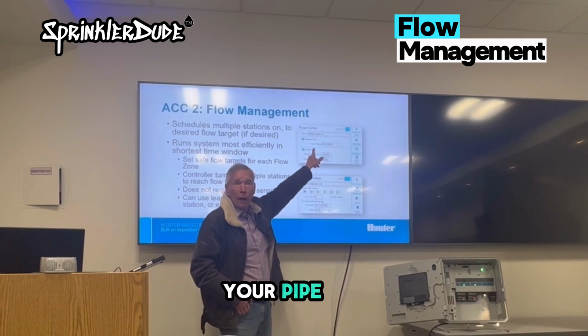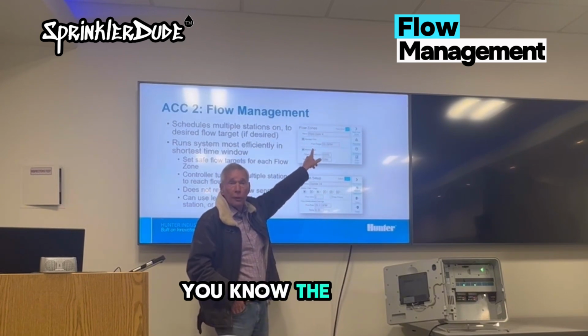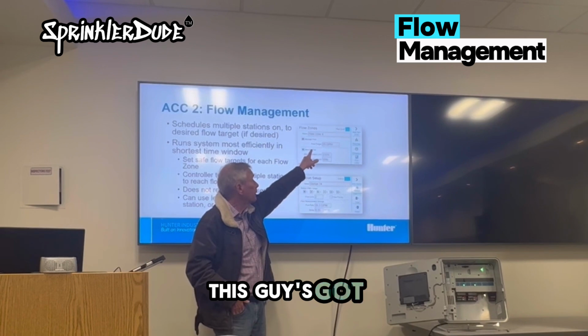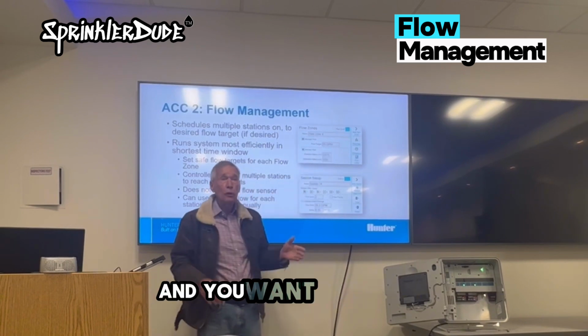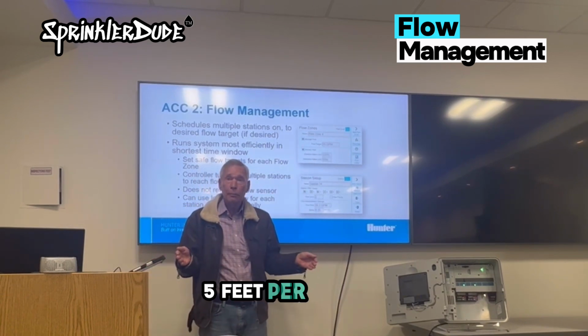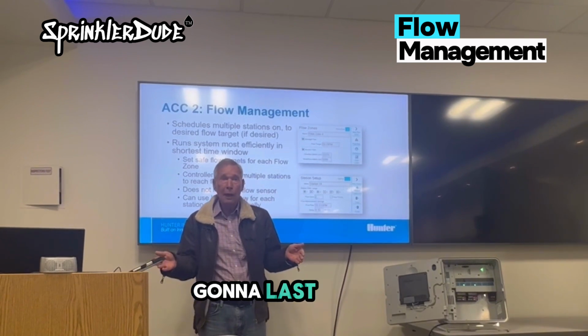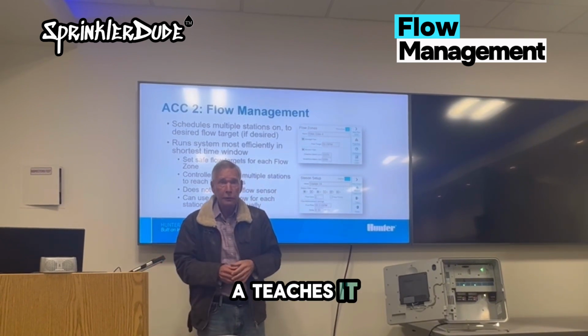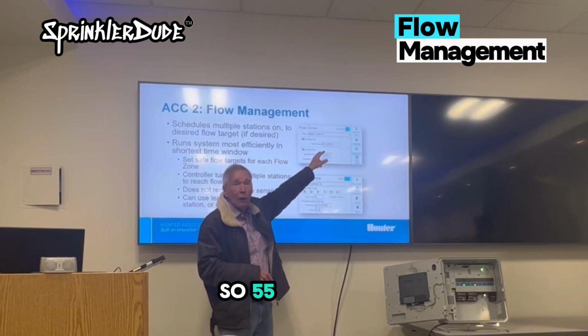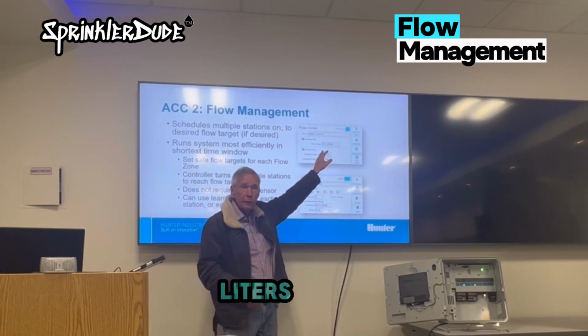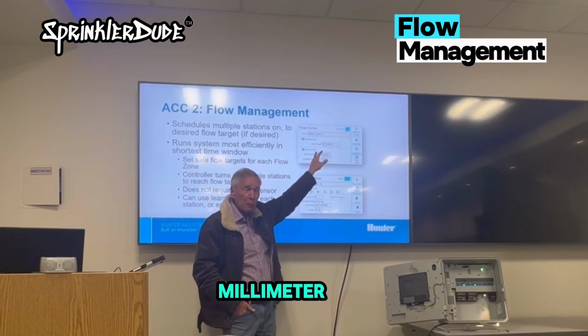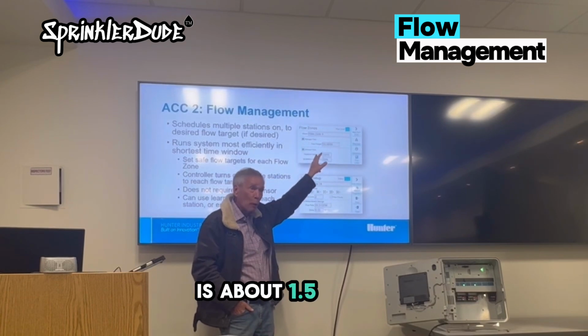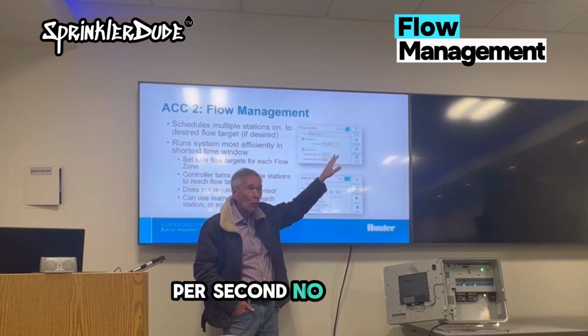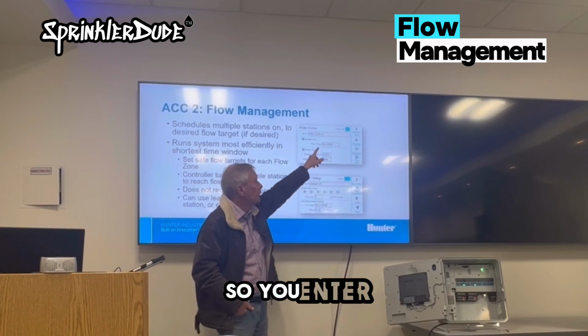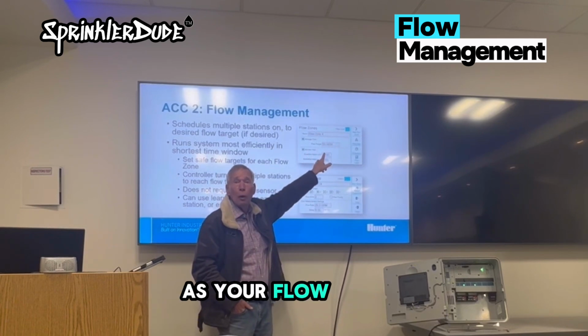If you know your pipe size, you know the target velocity. So this guy's got a 2-inch main line, and you want your flow to be about 5 feet per second because all your hardware is going to last longer, and that's how the IA teaches it. So 55 gallons a minute, which is a bunch of liters, in a 50 millimeter pipe is about 1.5 meters per second. No problem, that's where you want to be. So you enter that in here as your flow target.